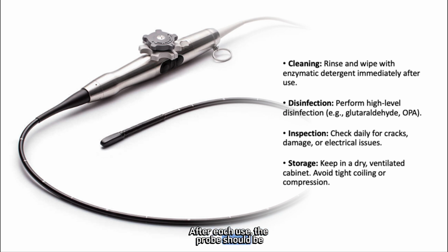After each use, the probe should be rinsed with enzymatic detergent and disinfected using glutaraldehyde or OPA. It must be inspected daily for cracks or electrical issues. Store in a dry ventilated cabinet, avoiding tight coils or compression to preserve its integrity.